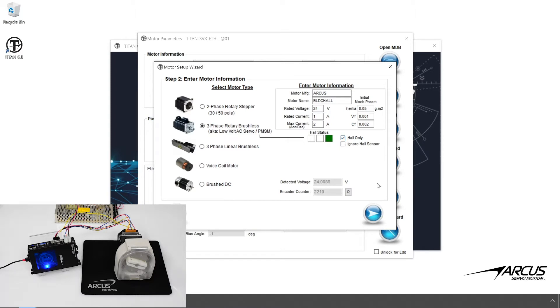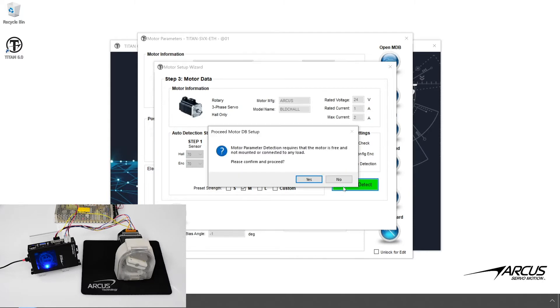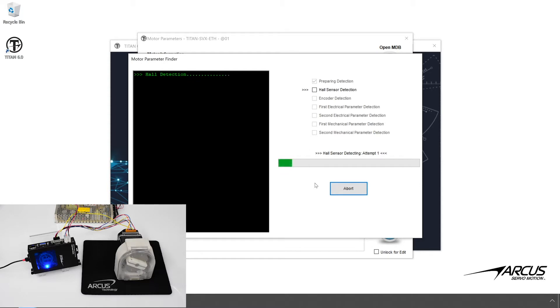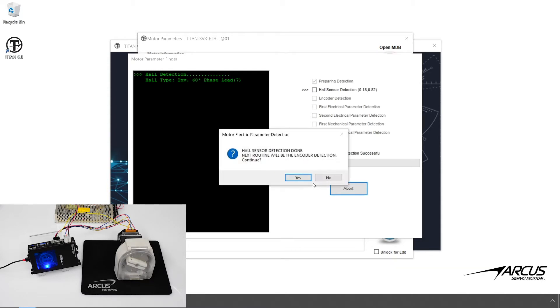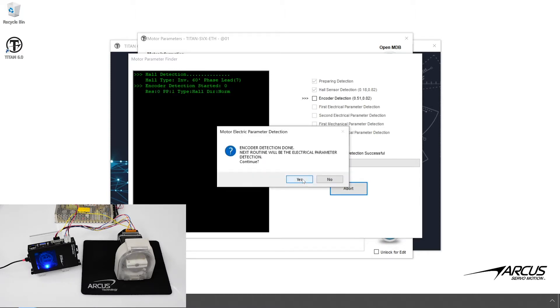We will now run the auto-detect routine. First, the software will detect the Hall Sensor arrangement. Then the software will check the encoder. As there is no encoder input on this motor, the resolution will be detected to be zero.